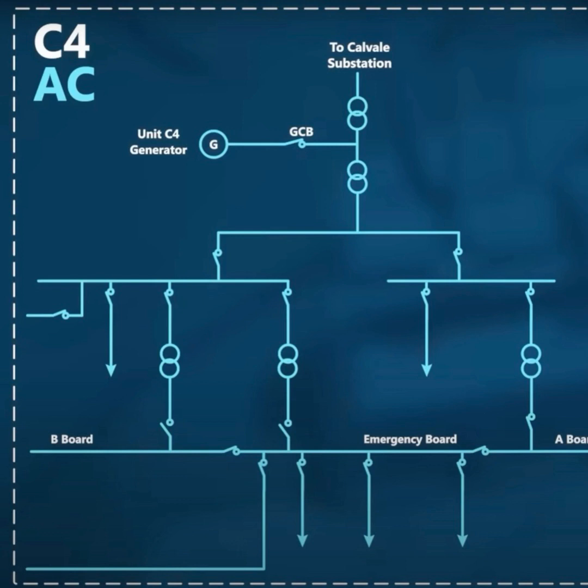After all, you can still tell the state of a breaker when you're in front of that breaker, just not what's connected to what else on the switchboard with just a glance. Even so, it's generally required that an SLD is kept on display or accessible within a switch room, and that can be kept in drawers in the room or more commonly displayed on the wall nearby. So the likely reason they didn't switch it manually is that when you're under that kind of pressure, information at a glance is crucial.